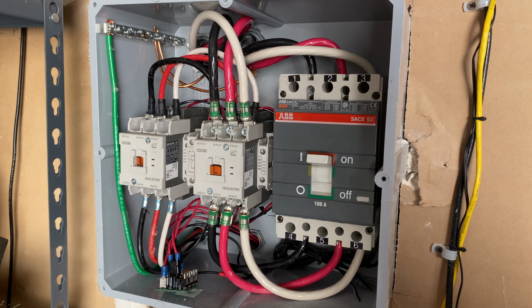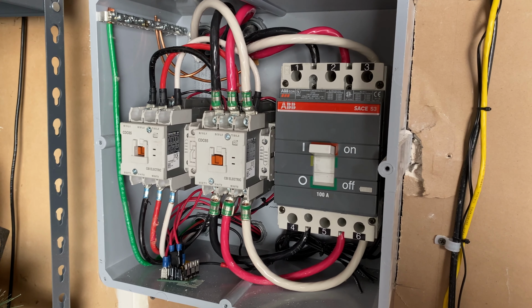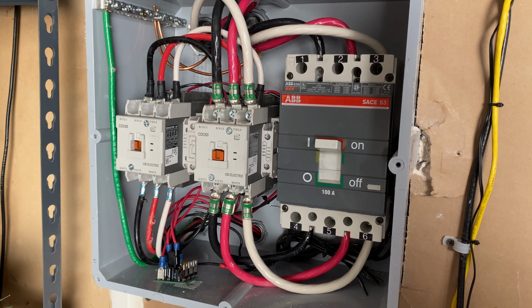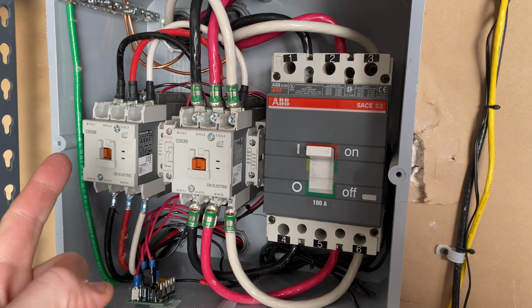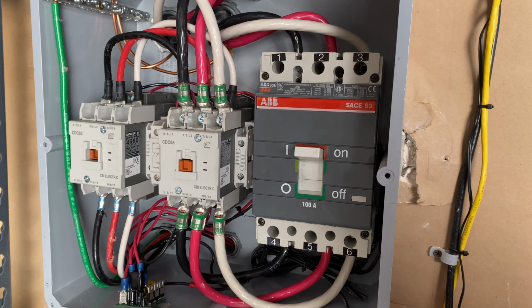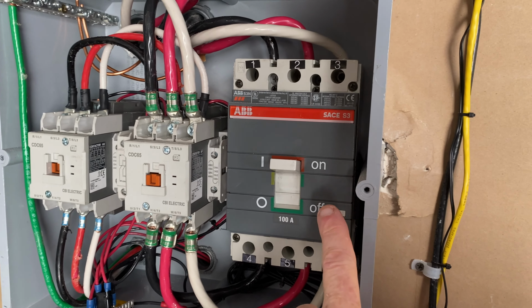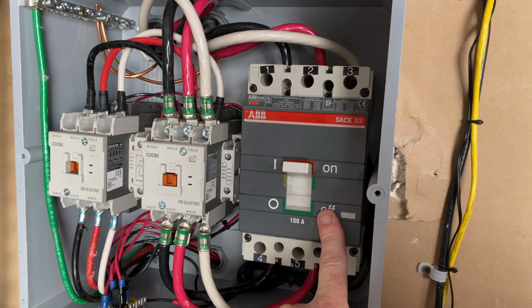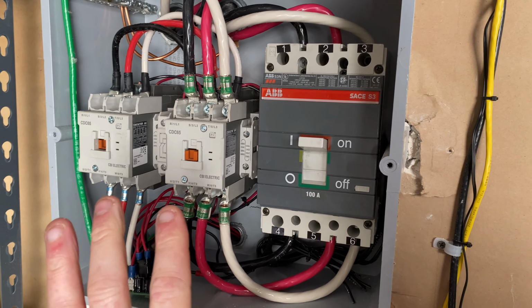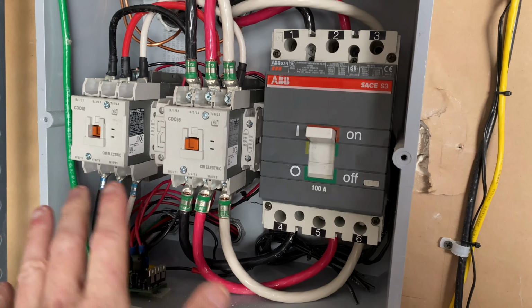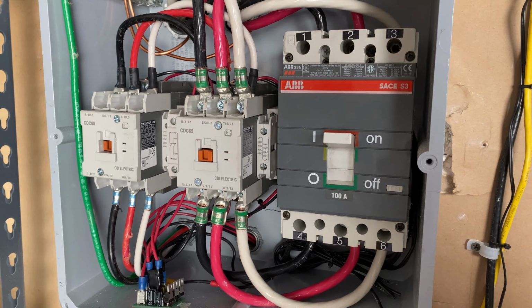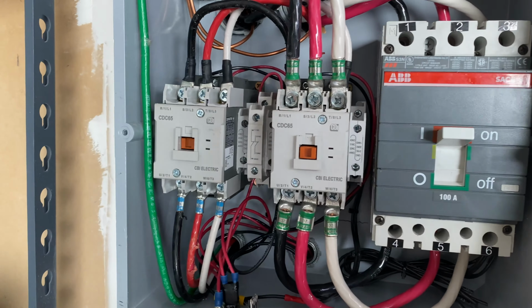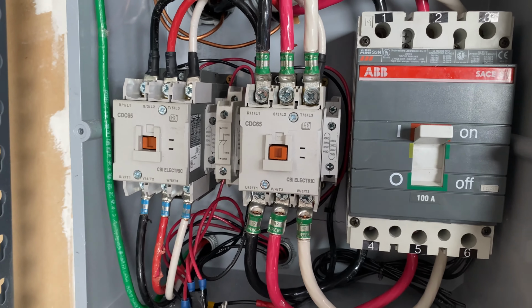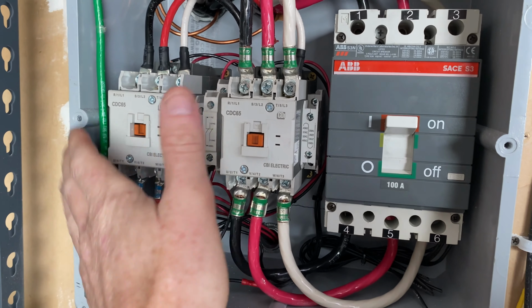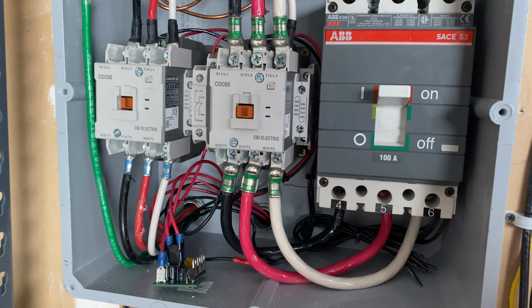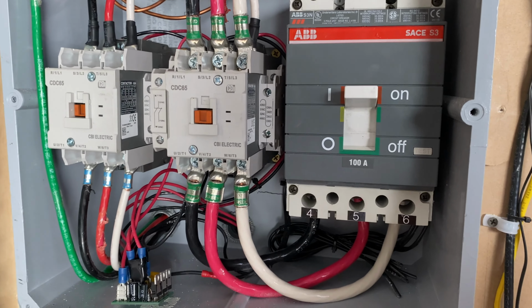All right, so here we are over at the automatic transfer switch on the inside wall of my garage. You can see here we have two rather large contactors. These are 100 amp contactors, 3 poles. This is a big breaker, but it's also a shunt trip. So it has a shunt trip that's controlled by the state of these contactors. So it's kind of like the last defense. If, for whatever reason, the mechanical interlock fails, and these ever get in the same state, it'll actually trip this breaker. So it protects basically the inverter and the grid from itself.